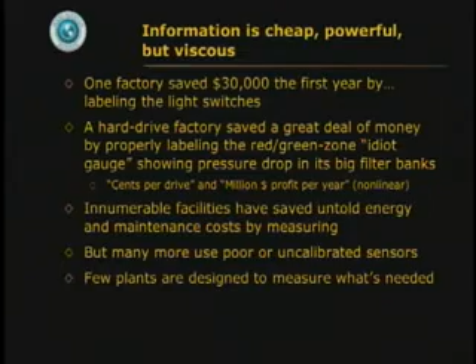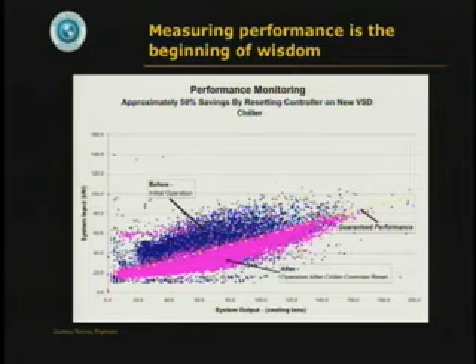And very few plants, even if they get the measurements right, give them to the operator in real time in effective graphics. Our colleague Peter Rumsey in Oakland had a chiller that was performing about twice as badly as the guaranteed performance, the yellow line. When measured carefully, the operation fell on all these blue lines. Up is bad, that's more energy use per unit of cooling. It turned out that the controls on the chiller had been set improperly, and when set properly, it worked the way it was supposed to, down in the magenta zone. But if he hadn't measured it meticulously, it would still be using twice the energy it's supposed to, and nobody would have known.